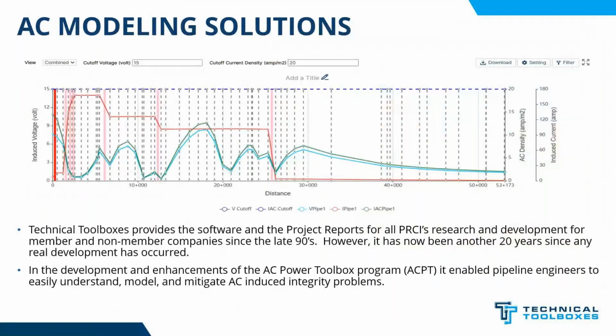In other words, what you'll see are these voltage spikes and AC current spikes that are quite high. You see all these peaks. This is what we're trying to do, and what we've done is lower the peaks. Remember, I'm trying to keep these peaks down below 20 amps per meter squared and below 15 volts for safety. And you notice I flattened this out.